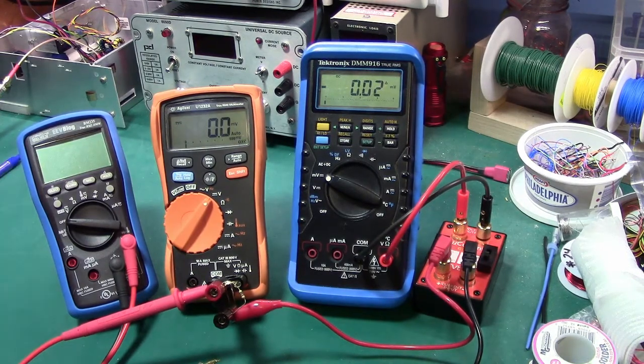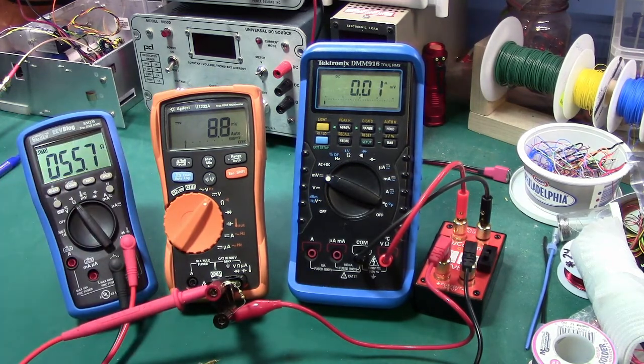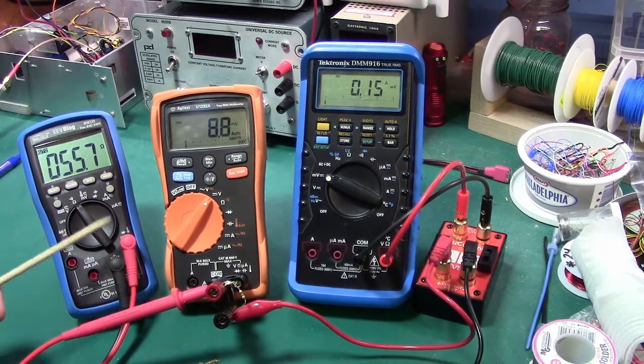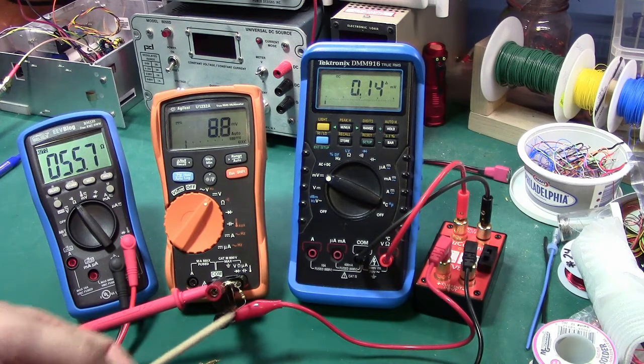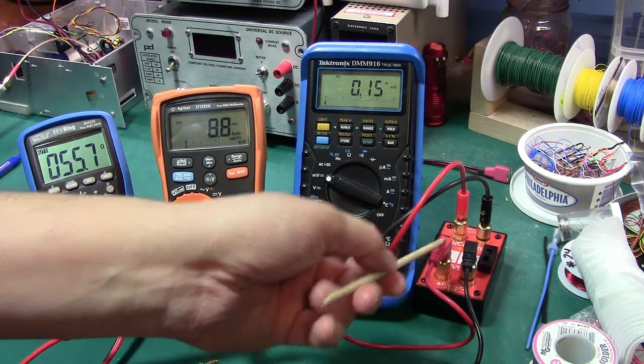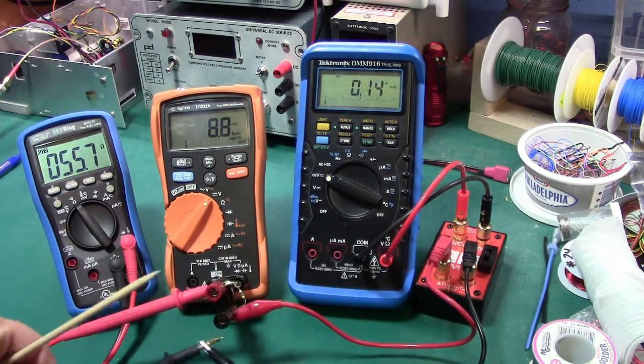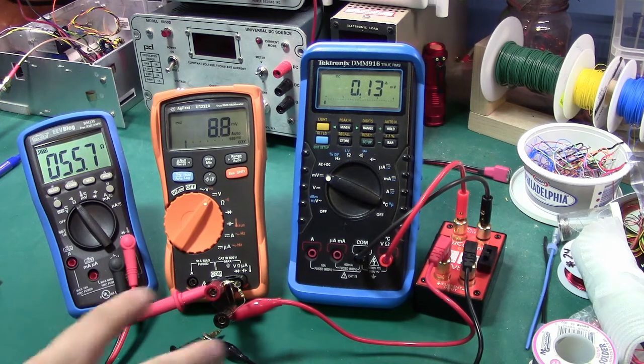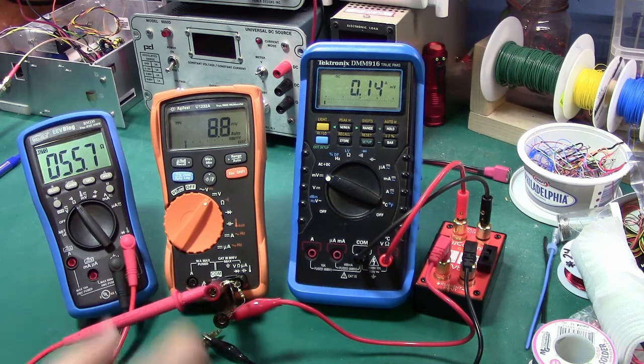Alright so I've got this set, I'm going to set this nominally at one millivolt per milliamp right now and we'll see what we get. So let's go ahead and turn this on. Everything's connected up, we've got our meter under test connected to our device here which is a 56 ohm resistor. That's going into the positive lead on our microcurrent. The negative coming out to the negative lead of our multimeter under test, and our meter here probing both leads of the device under test.